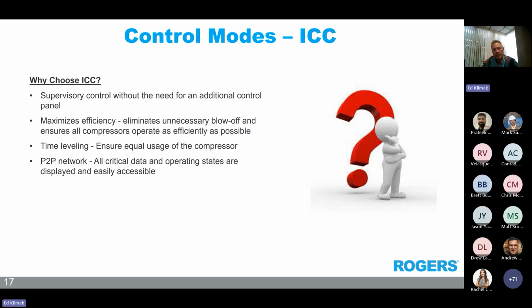So some of the key points: why would we want to use integrated compressor control? It's great for a supervisory control system to maintain constant downstream pressure when operating several compressors in a single header. It's great for automatic starting and unloading and loading of multiple compressors due to changes in demand. Requirement or need to rotate a single or multiple standby compressor into operation without any operator interaction. Requirement or need to communicate critical operating data across multiple compressors.